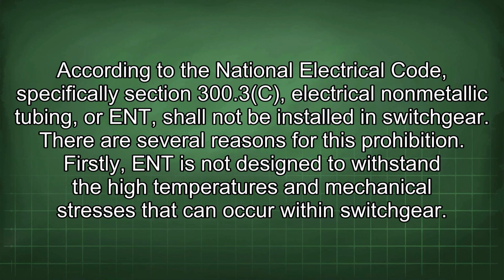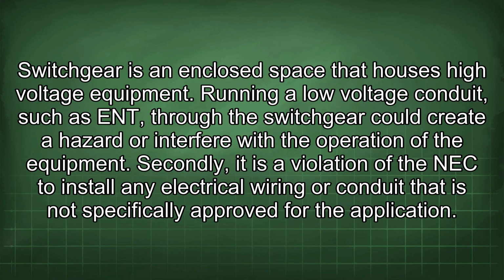According to the National Electrical Code, specifically Section 300.3(C), electrical non-metallic tubing, or ENT, shall not be installed in switchgear. There are several reasons for this prohibition. Firstly, ENT is not designed to withstand the high temperatures and mechanical stresses that can occur within switchgear. Switchgear is an enclosed space that houses high-voltage equipment.